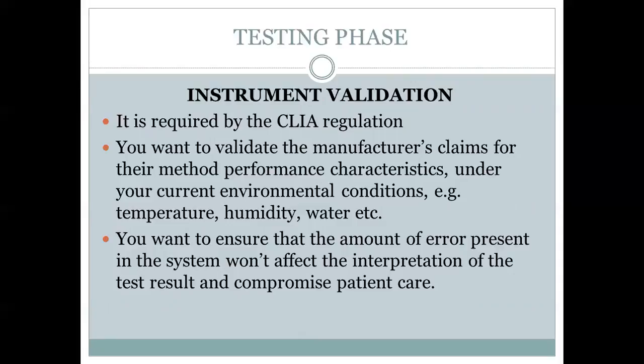And we also want to validate the instrument to validate the manufacturer's claims for their method performance characteristics under our current environmental conditions. For example, our temperature, our humidity, our water. So we want to make sure that the instrument is performing as the manufacturer described, that it will perform in our condition, in our environment. And we also want to make sure that the amount of error present in the system will not affect the interpretation of the test result and compromise patient care.